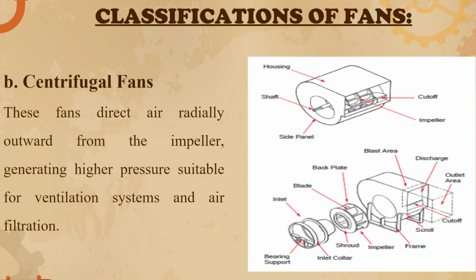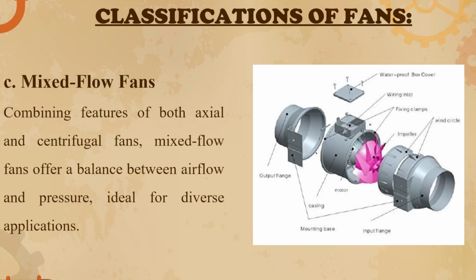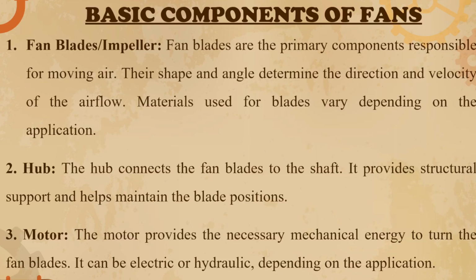The second classification of fan is the centrifugal fan. These fans direct air radially outward from the impeller, generating higher pressure suitable for ventilation systems and air filtration. Just like the axial fan, I have also presented an image of the components of a centrifugal fan, as shown on the right side of this presentation. The third classification is the mixed flow fan. Combining features of both axial and centrifugal fans, mixed flow fans offer a balance between airflow and pressure. It is ideal for diverse applications.